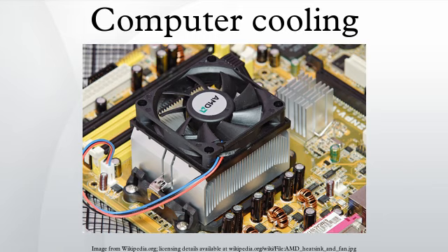A computer has a certain resistance to air flowing through the chassis and components. This is the sum of all the smaller impediments to airflow, such as the inlet and outlet openings, air filters, internal chassis, and electronic components. Fans are simple air pumps which provide pressure to the air on the inlet side relative to the output side. That pressure difference moves air through the chassis, with air flowing to areas of lower pressure.